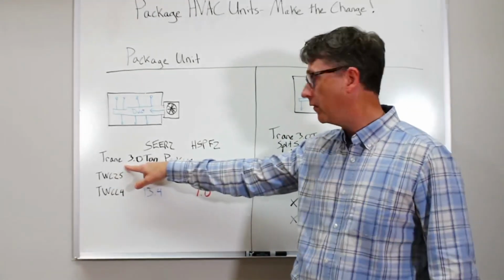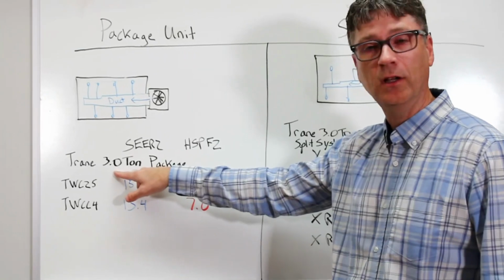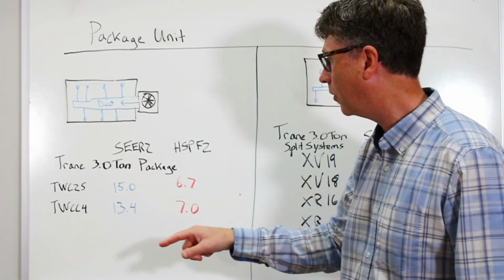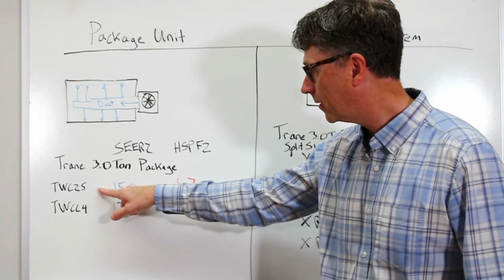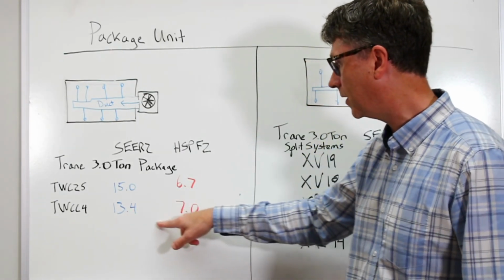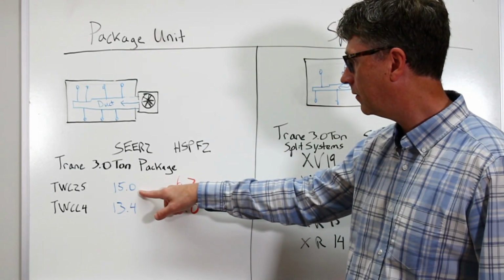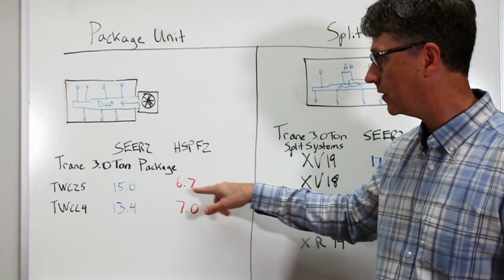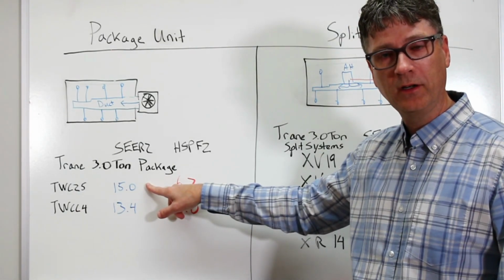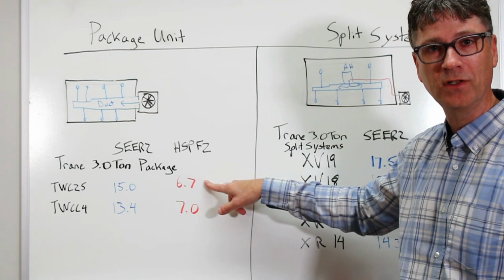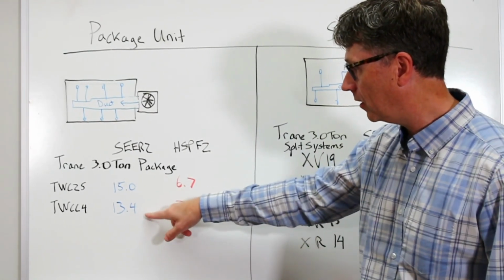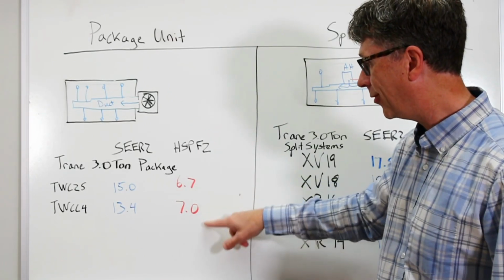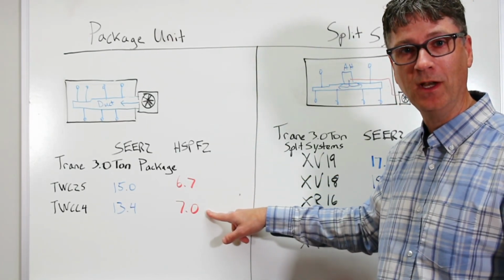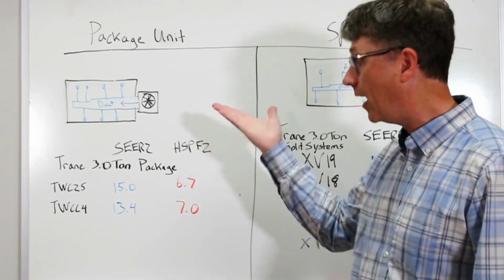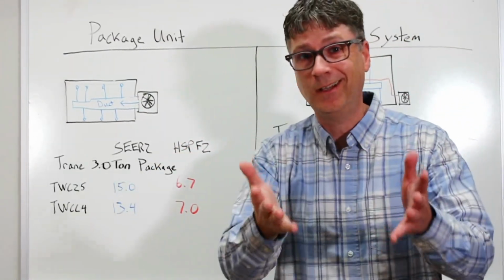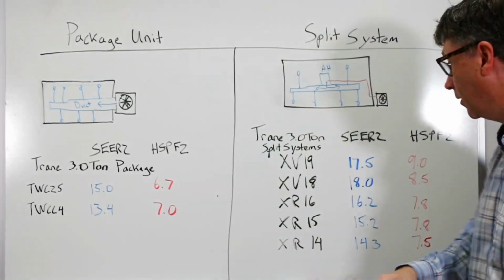Here's a Trane manufactured package unit in 3 ton, a pretty normal size for a house. They make 2 units: a higher efficiency one and a basic efficiency one. This is the SEER rating, and this is the HSPF rating. SEER measures efficiency for the air conditioning side, and HSPF measures efficiency for the heating side. 15 SEER or 13 SEER are your only options here, and you're only about 6.7 to 7 for HSPF. These numbers matter quite a lot. The higher the number, the more efficient your unit, the less you'll spend running it across the year.